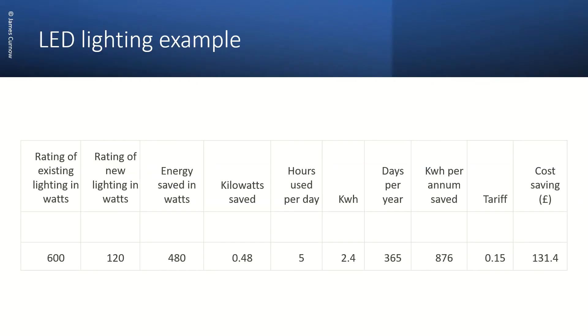Here is an example of how we can calculate the energy saving and present it in a way that could be used for a presentation or a business case. I have used the same scenario for the lighting in the house I mentioned a moment ago. Using a spreadsheet, I've put the value for existing lighting in watts. Then if we imagine that we are going to change the lamps for LED lamps which are 10 watts each, this would reduce the load to 120 watts with a saving of 480 watts or 0.48 kilowatts.